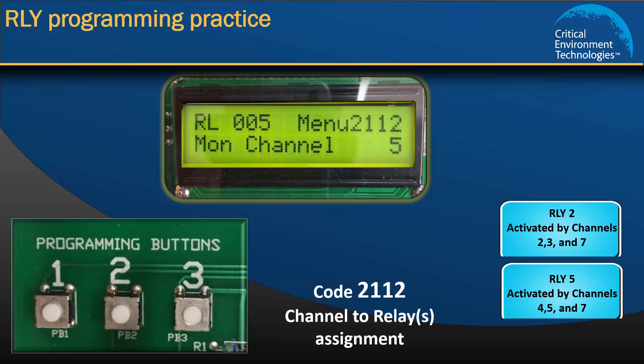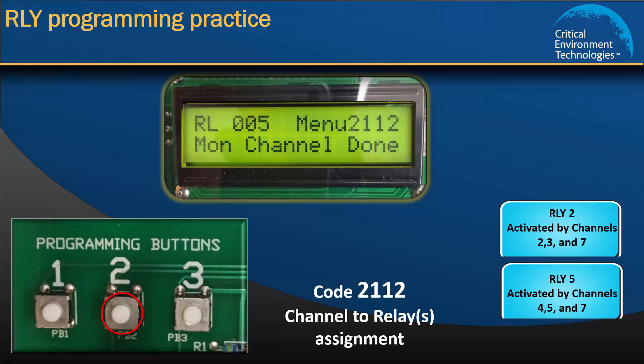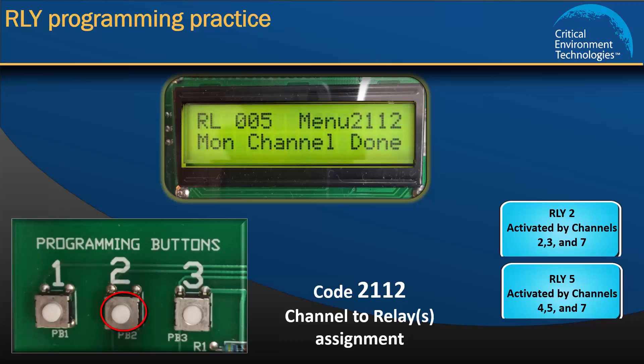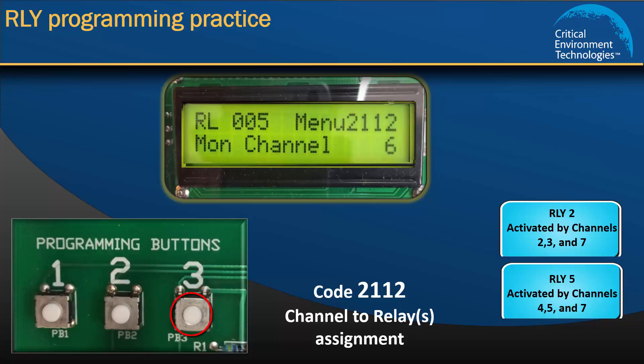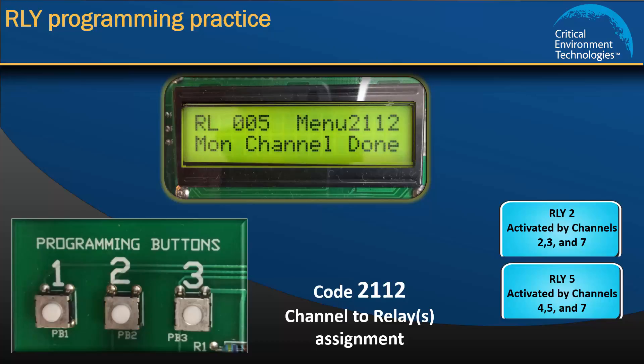By factory default, the display should show Relay 5, Channel 5. We want Relay 5 to be activated by Channels 4, 5, and 7. Press programming button 1 to decrease the Mon Channel number to 4 and press 2 to save. The display will show "Mon Channel done." Press 3 to increase the Mon Channel number to 5 and press 2 to save. The display will show "Mon Channel done." Press 3 to increase the Mon Channel number to 6, then 7, and press 2 to save. The display will show "Mon Channel done." Now we have assigned Channels 4, 5, and 7 to Relay 5.